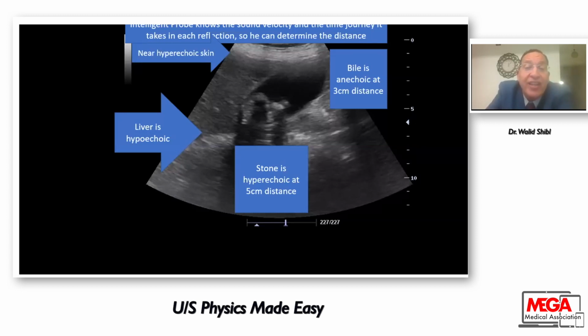And why is that? Because this intelligent transducer has two important pieces of information. First one, it knows the velocity of the sound. Suppose the velocity of the sound is 1 centimeter per second. And at the same time, this intelligent transducer knows the time of return of the reflected wave. So the reflected wave from the skin reached the transducer in 1 second, and it knows the velocity is 1 centimeter per second, so it will put the skin at a depth of 1 centimeter. The time of the reflected wave from the stone is 5 seconds. So it will put the stone 5 centimeters in depth. By translating the time to depth, the ultrasound picture will be constructed.